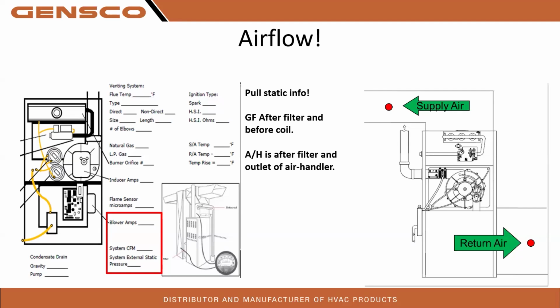Air handlers, it's inlet to outlet, right? So after filter, at the inlet, and then after heat strips, if it has it, because the coil is already taken into consideration from the manufacturer. So air handler is a little different than gas furnaces, but we're simply looking at total external static before the coil, after the filter, across the gas furnace, or across the whole air handler. Okay. So we're going to write that information down because that's going to tell us a lot.